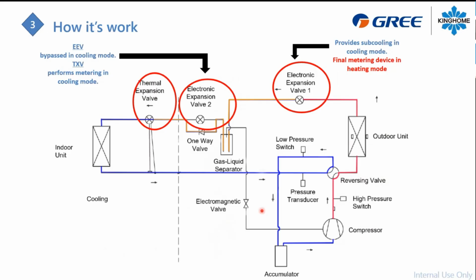So just to make a small review here on that diagram, just to make sure you understand it correctly, the first expansion valve here will provide subcooling in cooling mode. So just make sure you are 100% liquid refrigerant after that valve. But in heating mode, when the flow is reversed, it will act like your metering device. The second one here is bypassed when you are in cooling mode, and it will just make sure you are 100% liquid from the other side when it's in heating mode. So it will provide you subcooling in the heating mode, and then your thermostatic expansion valve is your metering device in cooling.